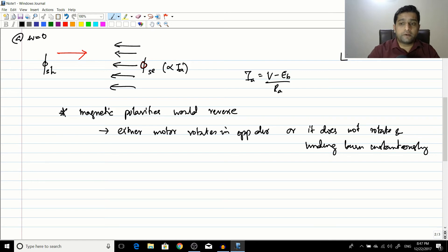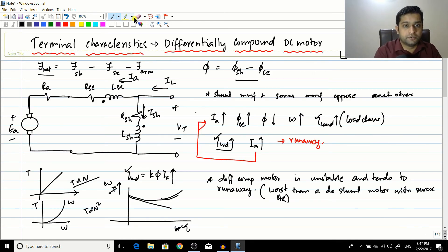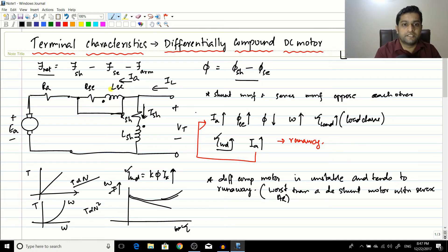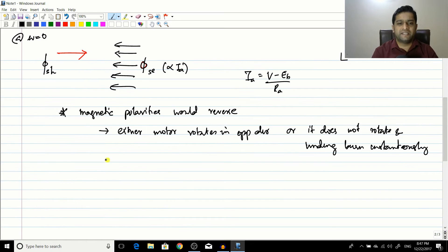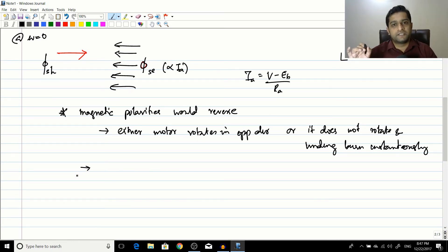If you want to start such a motor, you can short the series winding during starting so it has no effect. The current bypasses it, you apply the normal starting methods, and the motor starts. But in reality there is no application for differential motors.